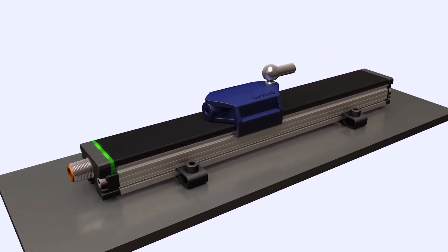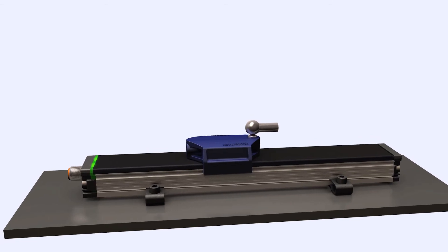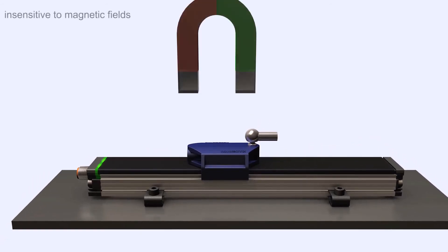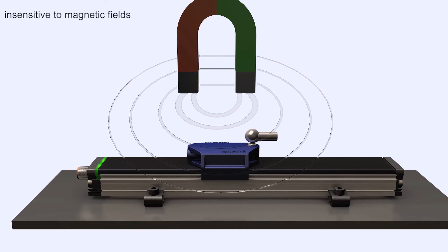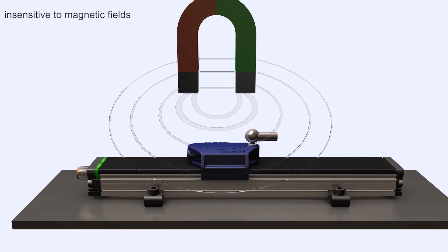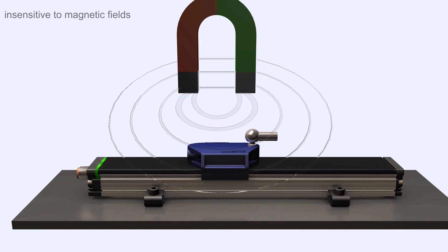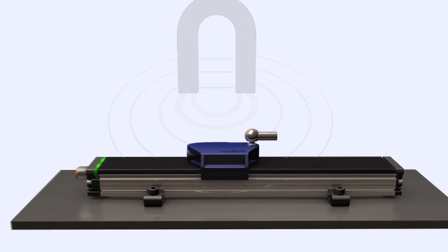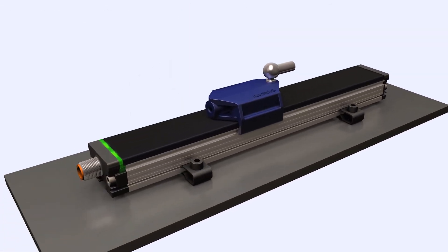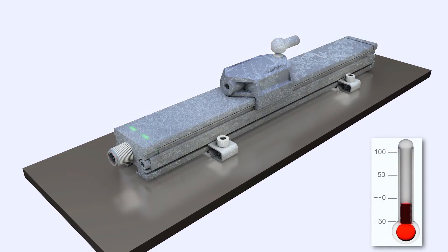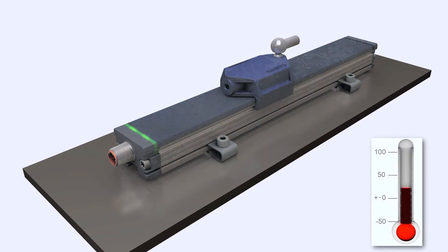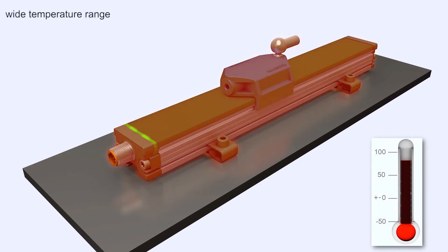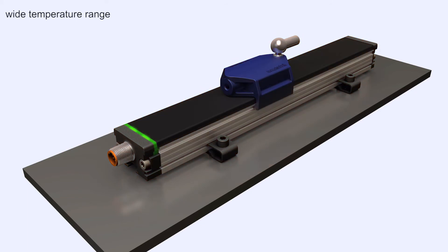NovoPad technology is insensitive to magnetic fields produced by powered devices like electric motors, hydraulic valve switches, or variable frequency drives, as the position is not detected by a magnetic field but by an inductive field. The TF1 series of sensors operates over a minus 40 to plus 85 degrees Celsius temperature range.